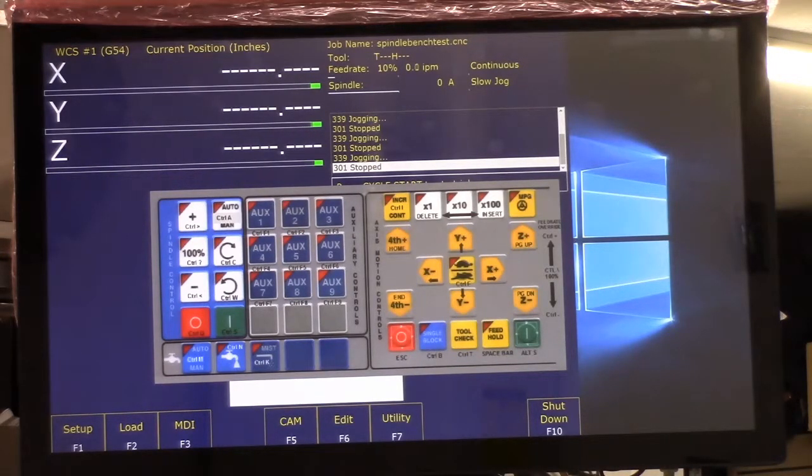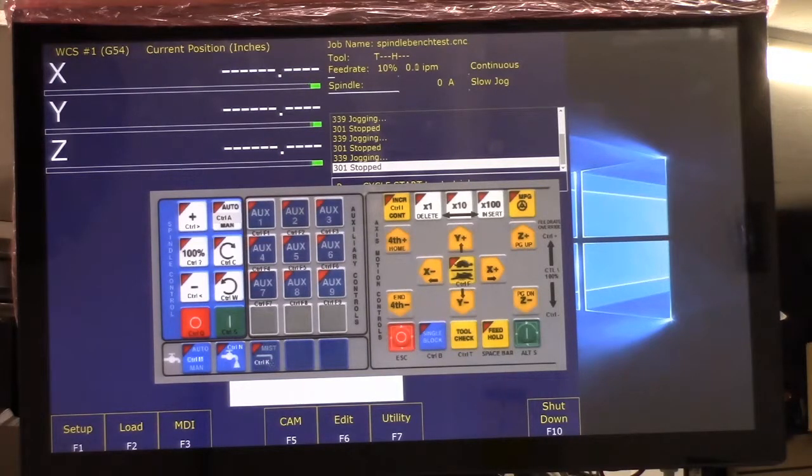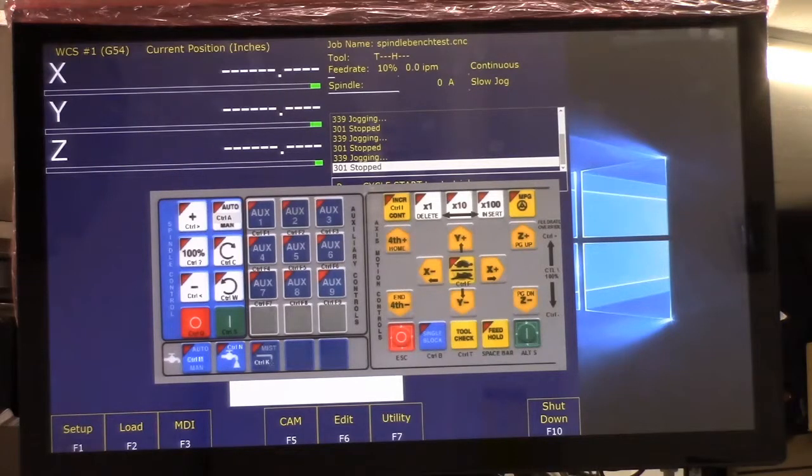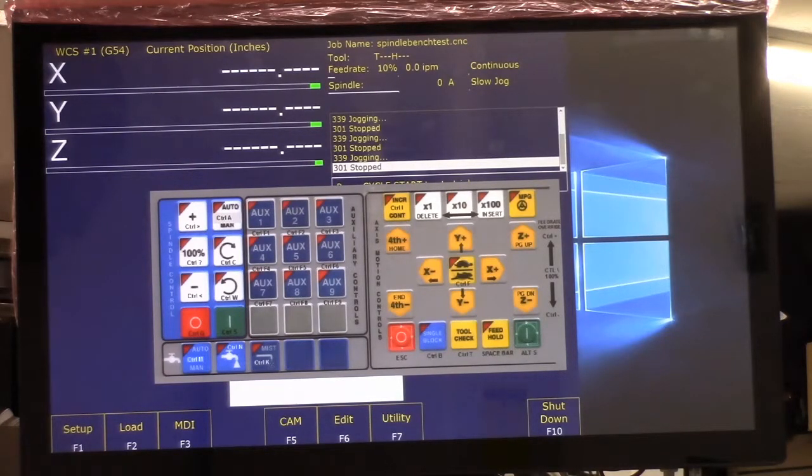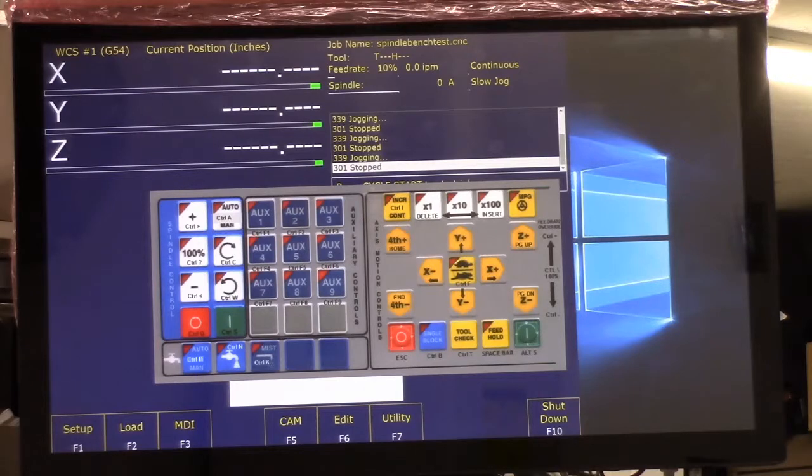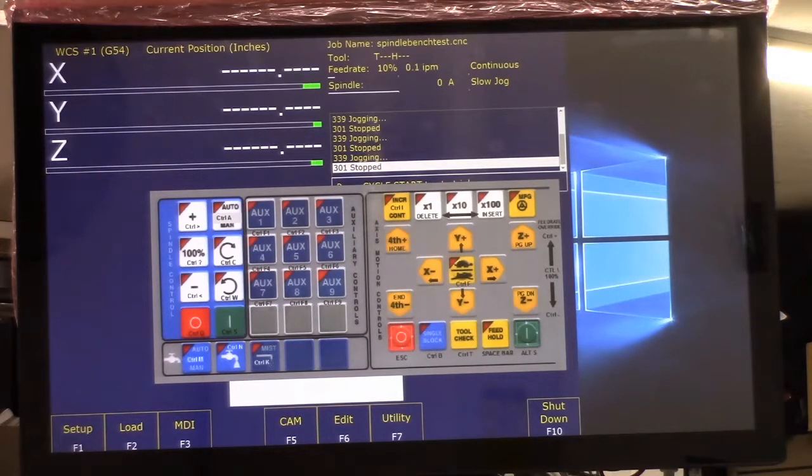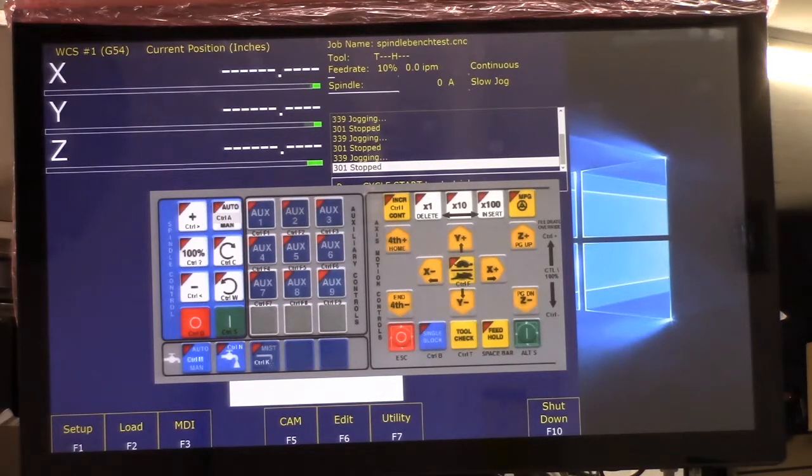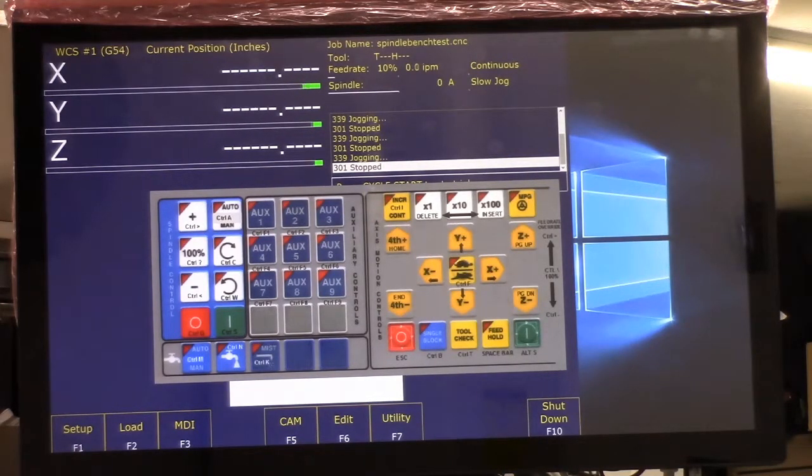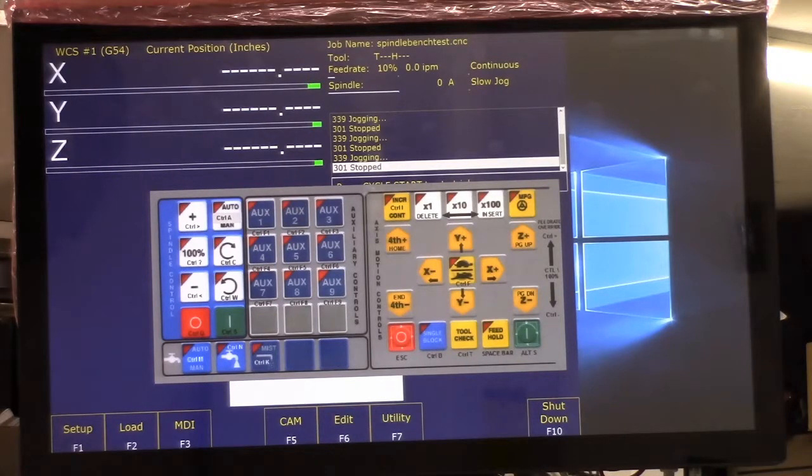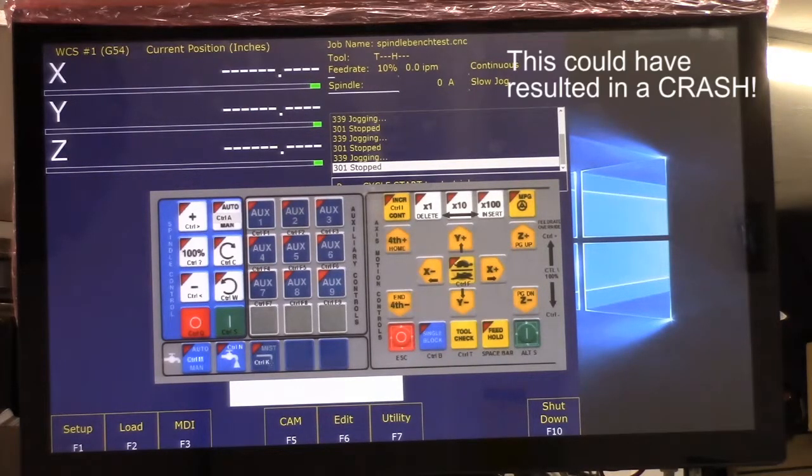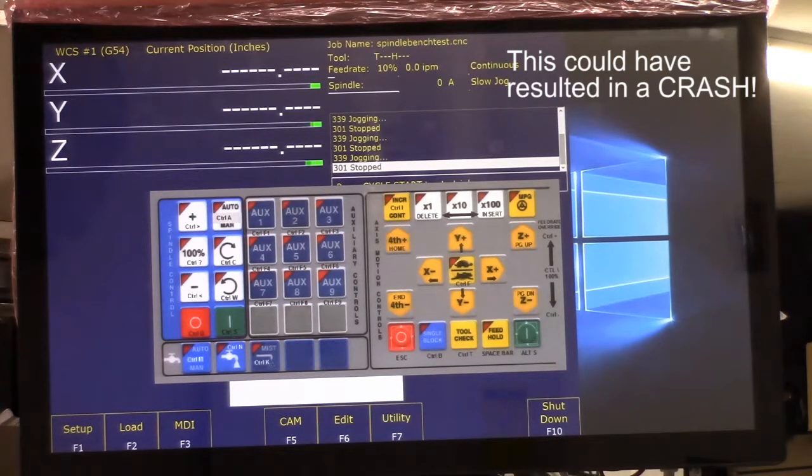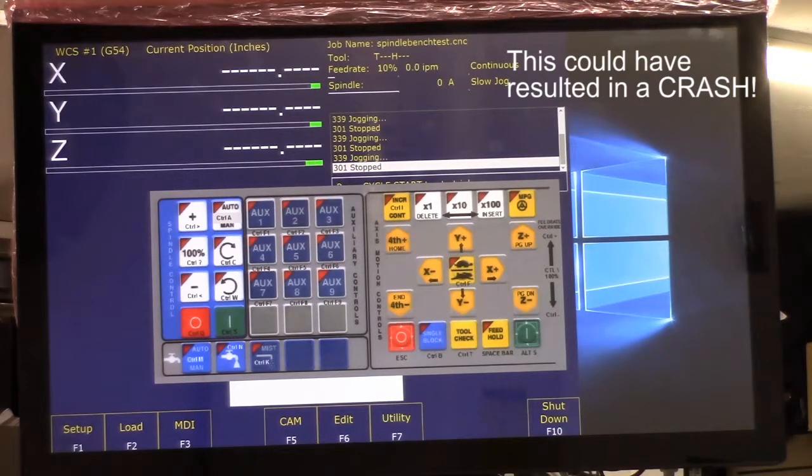And it says danger. The first time jogging the servo motor, it's best practice to have it disconnected from the machine, either physically removing the motor or removing the gear or drive belt. This way, if something goes wrong, there is minimal risk of mechanical damage to the machine. If one of the parameters or settings was entered incorrectly during the setup, a motor may oscillate violently or move out of control. And that's what I had. I had runaway, so had my belts been on and that runaway occurred, that table would have just gone flying, you know, or the Z would have just come down because it went full RPM on a motor.